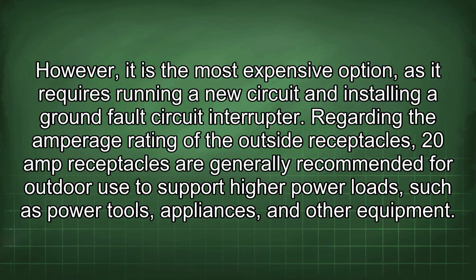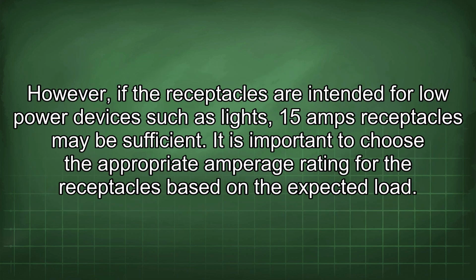interrupter. Regarding the amperage rating of the outside receptacles, 20 amp receptacles are generally recommended for outdoor use to support higher power loads such as power tools, appliances, and other equipment. However, if the receptacles are intended for low power devices such as lights, 15 amp receptacles may be sufficient. It is important to choose the appropriate amperage rating for the receptacles based on the expected load.